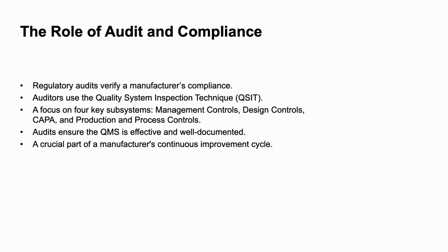Regulatory audits are a critical component of the post-market compliance landscape. As noted in the provided reference material, in the United States, the FDA uses the Quality System Inspection Technique, or QSIT, to conduct inspections. QSIT is a risk-based approach that focuses on four key subsystems of the QMS: management controls, design controls, corrective and preventive actions, CAPA, and production and process controls. An auditor will use this framework to verify that a manufacturer's QMS is effectively implemented and maintained.